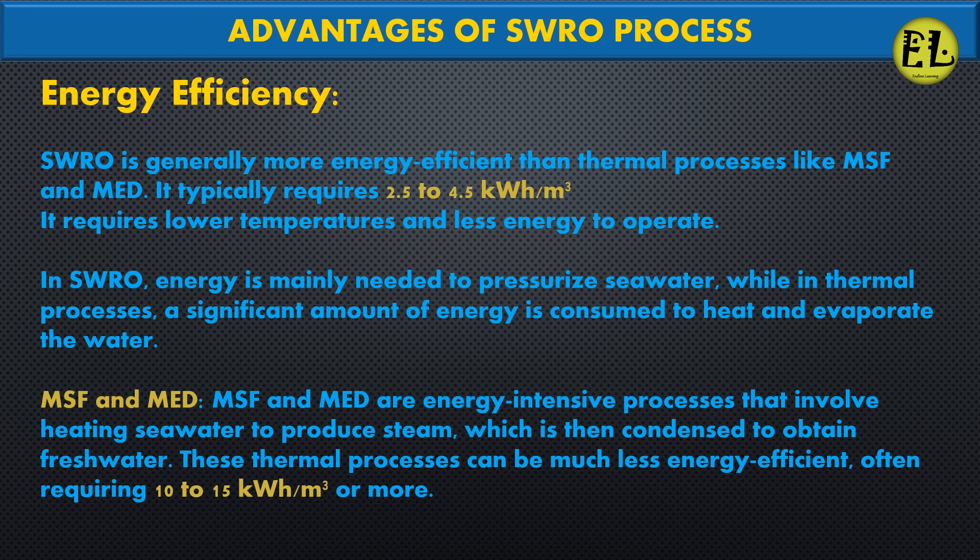MSF and MED are energy-intensive processes that involve heating seawater to produce steam, which is then condensed to obtain fresh water. These thermal processes can be much less energy efficient, often requiring 10 to 15 kilowatt hours per cubic meter or more.